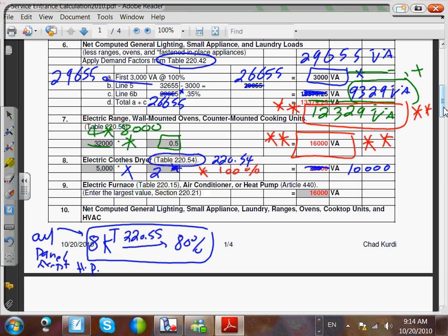So how about the house panel? Are you guys following what I say? We have 6 panels. The main panel is what I'm sizing right now. That's the one that feeds everything. The main panel, the main service and the service entrance equipment. Then underneath it, I'm feeding 5 panels: 4 for the 4 apartments, and 1 for the house panel. Okay. So this calculation is for the main service entrance panel.